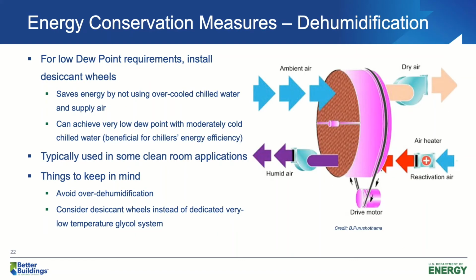The final energy conservation measure for airside equipment is about dehumidification. Typically for modest dew point applications, our chilled water system should be sufficient. But if you need a very low dew point, you will have 2 choices: to install a separate low temperature glycol system, or to install desiccant wheels into your air handling units. I will recommend desiccant wheels because you do not have to maintain another set of chillers and pumps.